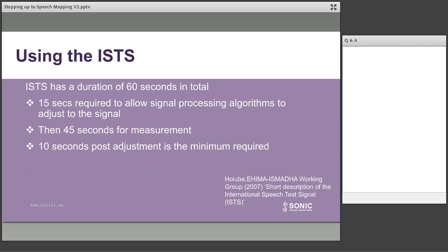So when you're using the ISTS, it's important that you know a bit more about it. We know that the first 15 seconds are required to enable all of the algorithms and the features to engage. So you need to run it at least for 15 seconds to start off with. And then there's 45 seconds more for measurement, and every time you make a change, you need to wait for at least 10 seconds after that change in gain to actually be able to see it.